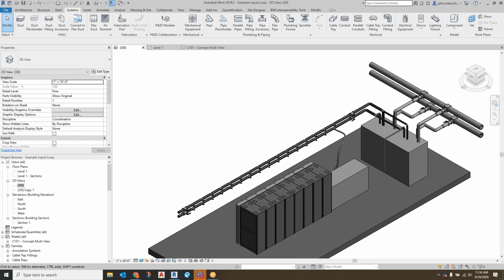Just to give a little background on the conversation that Don and I, and John Minash, were having earlier this week. The thought behind the connection size discussion was really more for the IT managers, the IT planners, trying to figure out at a high level if it's even feasible to put this much load in a certain area. Basically by saying, if you've got 250 kW and your system is at a 5C delta T, then you need this size pipe connection to be able to handle that.